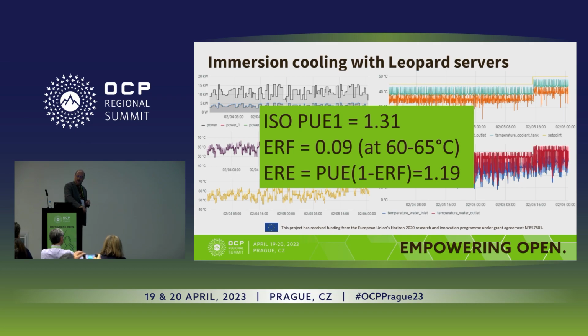And so 1.31 is quite high, right? But we are actually reusing the heat, because the data center is connected with the fuel cells that are producing the power to the data center, running off biogas, and is connected to the district heating. And we are supplying 60 to 65 degrees of heat to the heating network. So the ERF, annualized over 1 year, is 0.09. This energy reuse effectiveness, which is not an ISO metric, is the PUE multiplied by 1 minus ERF, so that would be 1.19. And so if there was a mandatory requirement to be less than 1.2, it would make it. But 1.31 PUE wouldn't make it. And that's the point I was trying to make.